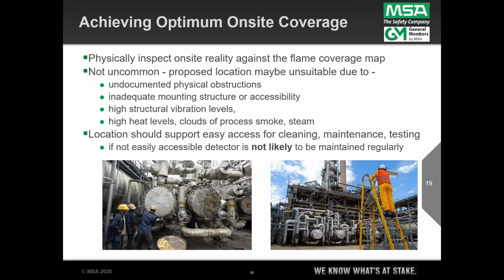Or the piece of structure where they wanted to put it is very, very flimsy. This is not going to work. Or there's high vibration. And I was at a job site once in Canada where a steam release vent was putting the flame detector in a constant state of dripping condensation. It's like, okay guys, this is not going to work.